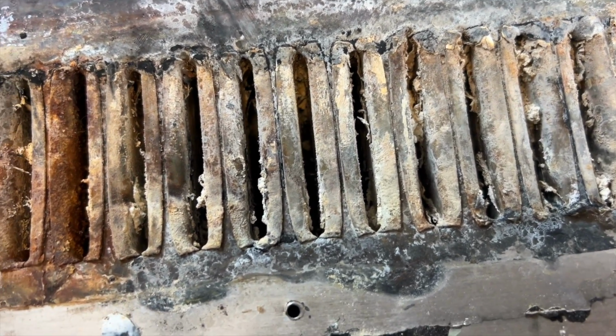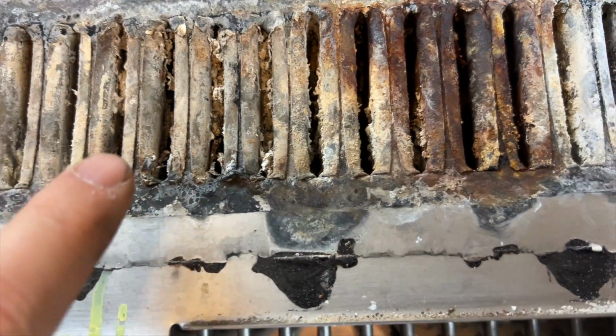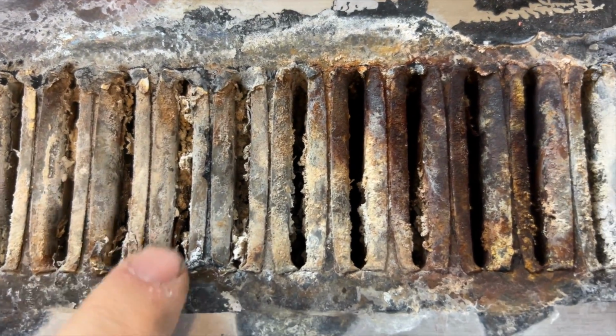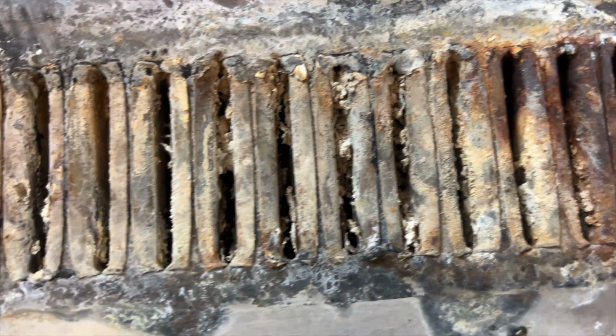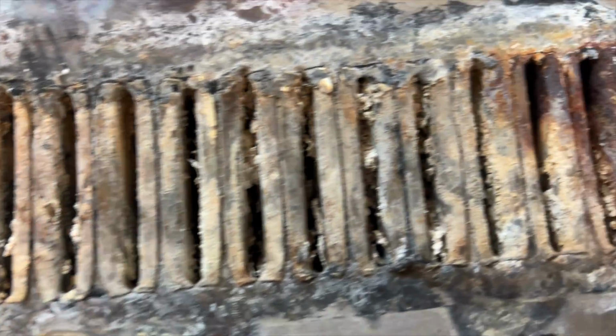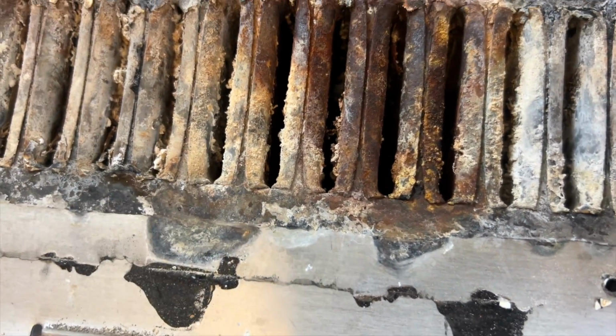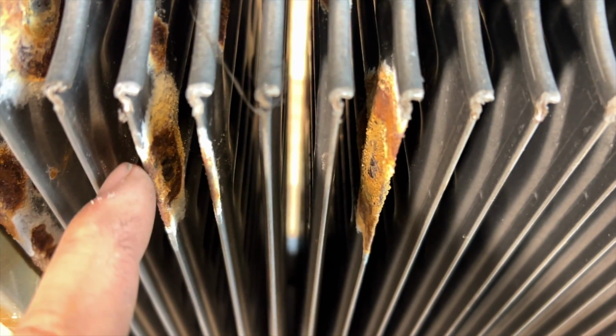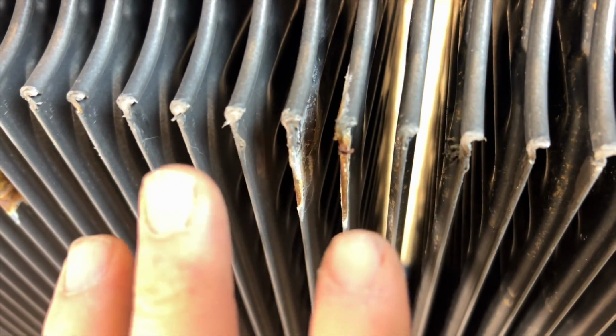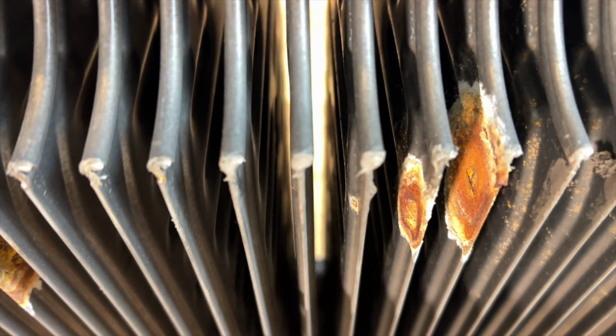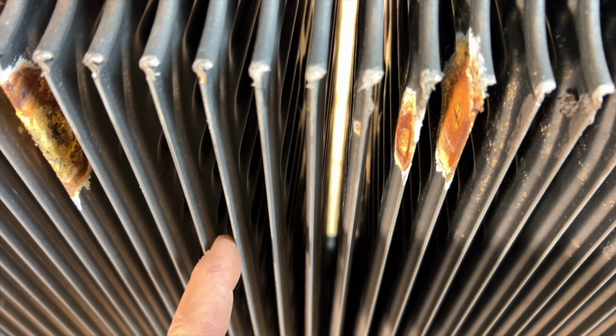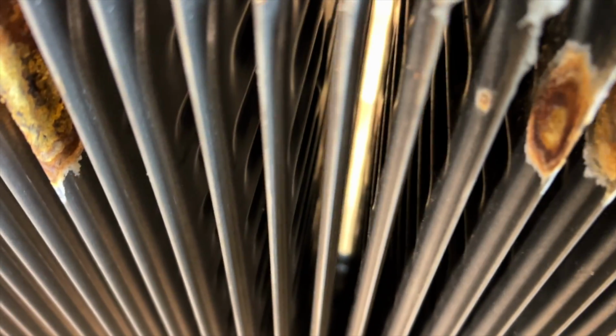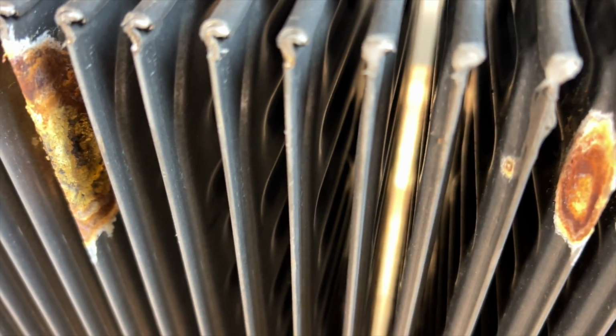What happens is as this was running, it was plugged up, the moisture gets stuck in there, it doesn't drain out properly, so this whole thing just gets full of water. And then it just deteriorates even more until it actually eats its way all the way through, and you start getting stuff like this. So this is why I don't like this particular design on the Carrier ones, and I think that's why they're starting to move away from this design. But like I said, as far as heat transfer goes, they work really well, because you can see in there, that's a lot of surface area.